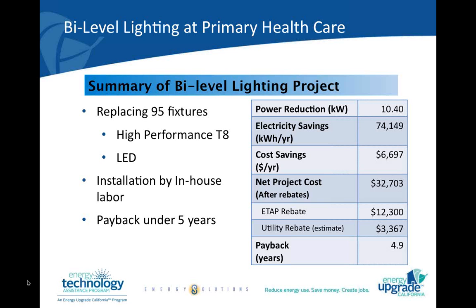We decided, based on the economics, that we would go with the high-performance T8 bilevel fixtures on the first floor, and then with the LEDs up on the top deck. We are going back, because of the better rebates that are available, now looking at LEDs also on the first floor. Some of the drivers for us on this were obviously the energy savings, in addition to the reduced maintenance cost. LEDs we know have a longer life cycle, and so that really can reduce our maintenance costs. So even though when we do our projects we can't count that in the payback, it is a direct benefit to our operations.